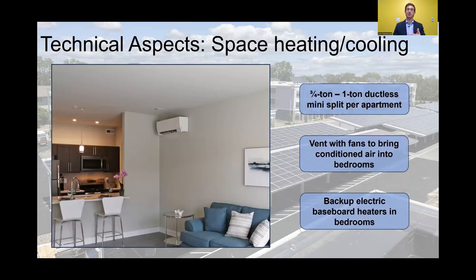Speaking of space heating and cooling things down, they were able to size the 1 unit apartments with a 3/4 ton unit and the 2 unit apartments with a 1 ton ductless mini split. That may seem tiny, but because the buildings are so airtight and so well insulated, it doesn't take all that much to heat and cool a space. And they put this single head mini split in the living room. You might be wondering, how does that get into the bedrooms?